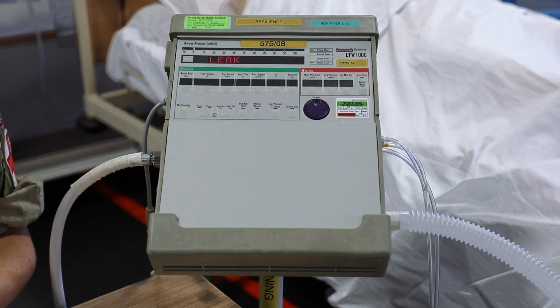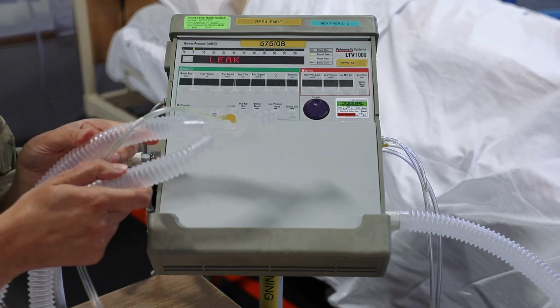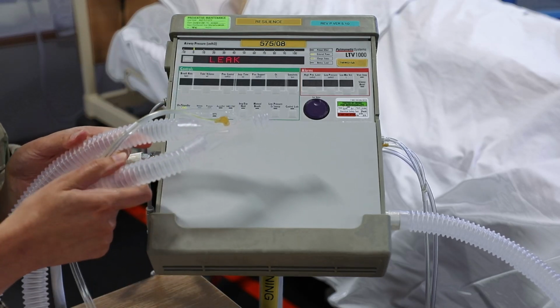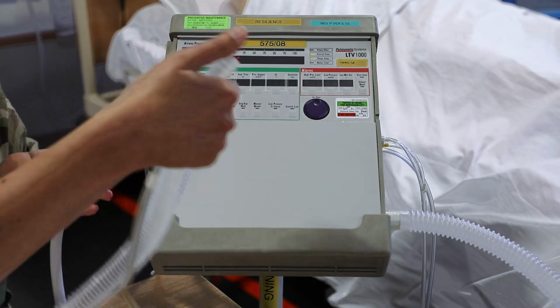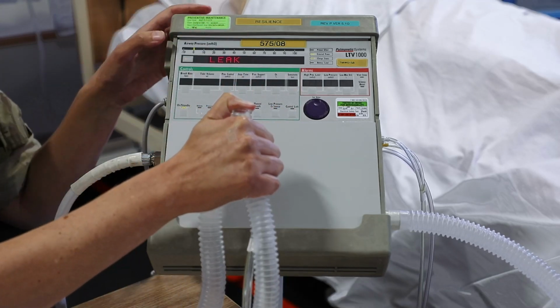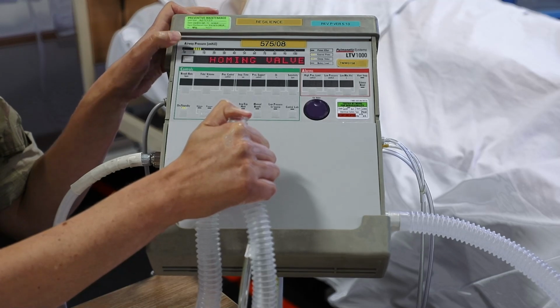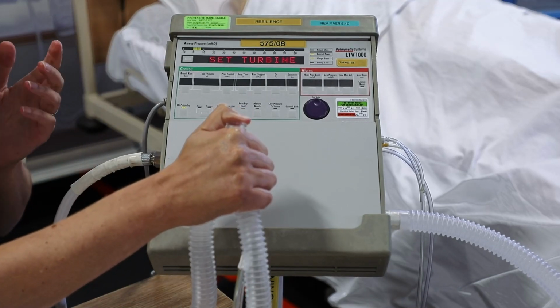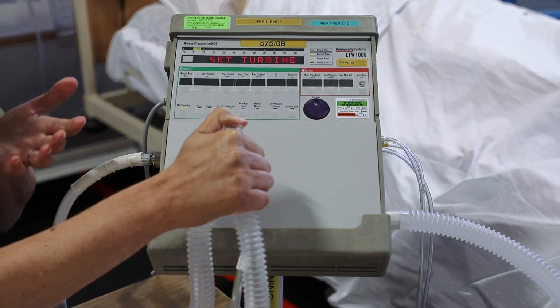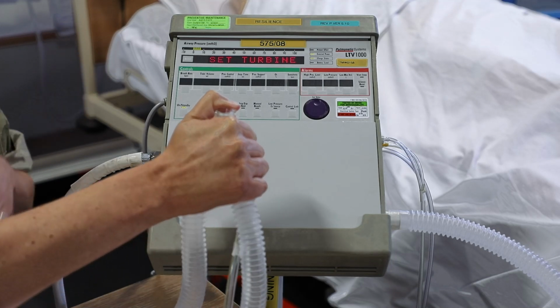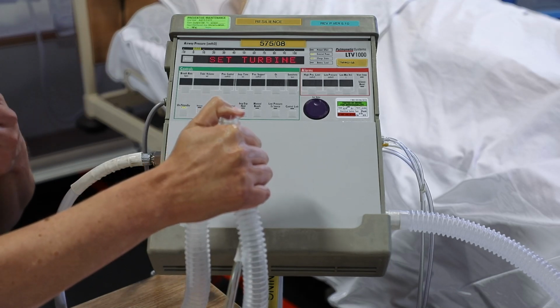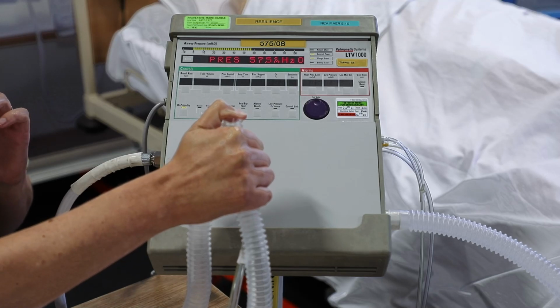Here we're going to perform the leak test, and to perform that we're going to need to occlude the Y piece of the ventilator. We can just do that with a thumb, so just place your thumb over the Y piece and press select. What we're looking for here is to confirm that it achieves a pressure of greater than 45 centimetres of water, and that we don't have a leak of any more than a litre.